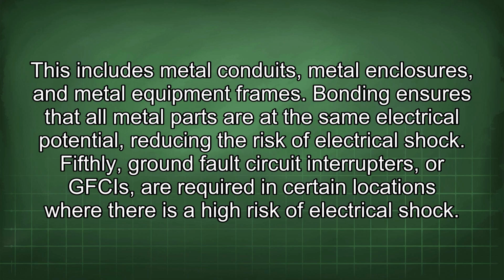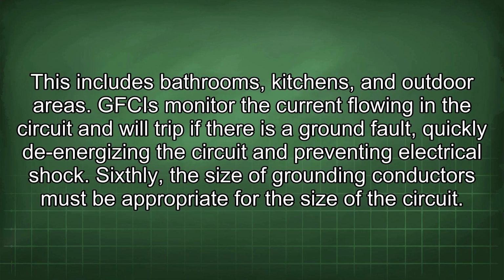Fifthly, ground fault circuit interrupters, or GFCIs, are required in certain locations where there is a high risk of electrical shock. This includes bathrooms, kitchens, and outdoor areas. GFCIs monitor the current flowing in the circuit and will trip if there is a ground fault, quickly de-energizing the circuit and preventing electrical shock.